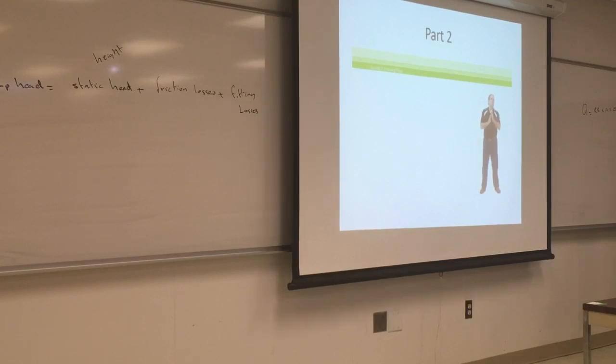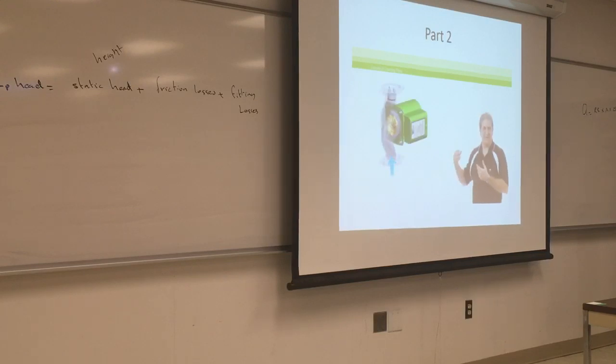Here's an overview of the Taco double O family cartridge circulator in action. You can see that the water enters the casing, also known as the volute, right about here. Then the water is pulled into the eye of the impeller, and the impeller drives it to the outside. This force to the outside is the centrifugal force. It's this action that adds velocity to the water, and along with the shape of the volute, creates the higher pressure before the water leaves the circulator over here.